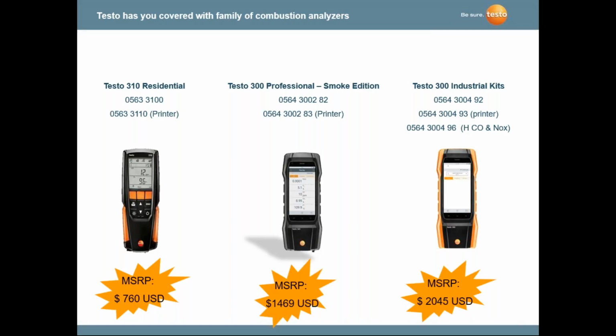And then the industrial version really includes 3 sensors, the addition of 3 sensors, which is the oxygen, the carbon monoxide, and the NOx sensor. So we're addressing all the markets there, whether you're doing residential oil or if you're doing gas utility boilers.